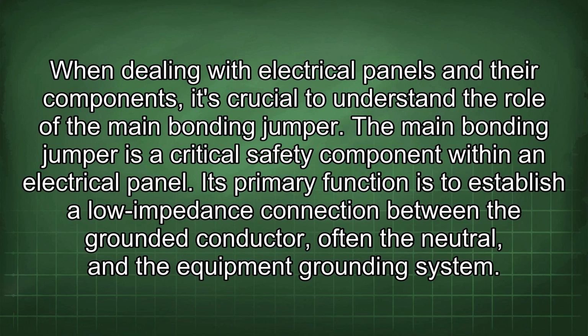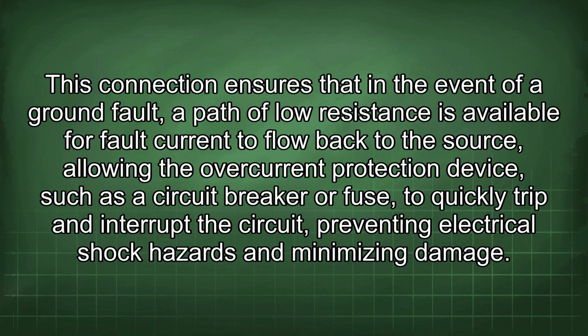When dealing with electrical panels and their components, it's crucial to understand the role of the main bonding jumper. The main bonding jumper is a critical safety component within an electrical panel. Its primary function is to establish a low impedance connection between the grounded conductor, often the neutral, and the equipment grounding system. This connection ensures that, in the event of a ground fault, a path of low resistance is available for fault current to flow back to the source, allowing the overcurrent protection device, such as a circuit breaker or fuse, to quickly trip and interrupt the circuit, preventing electrical shock hazards and minimizing damage.